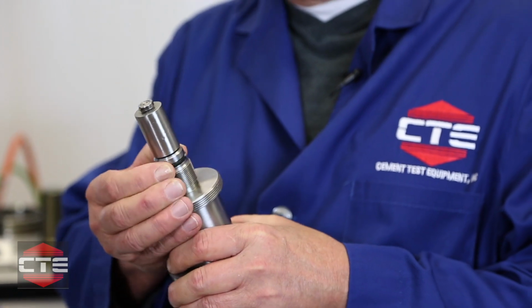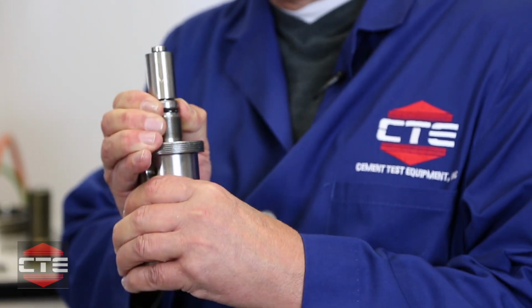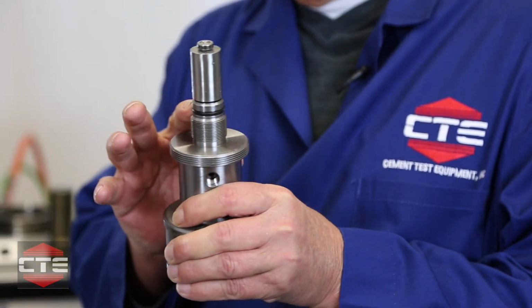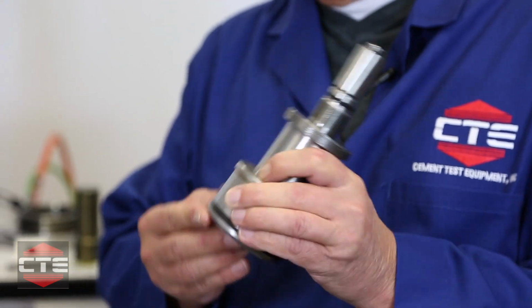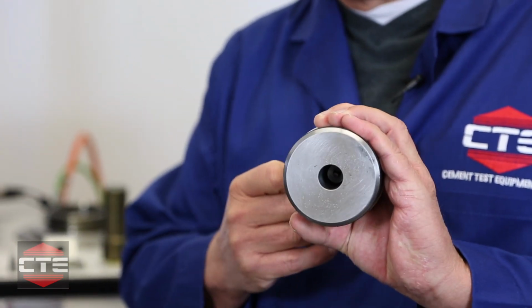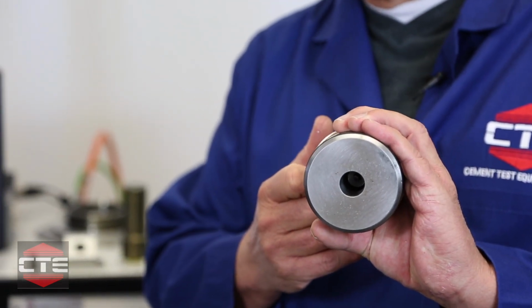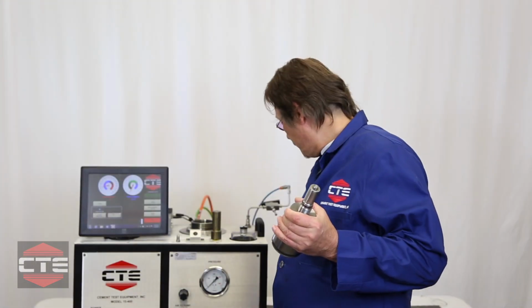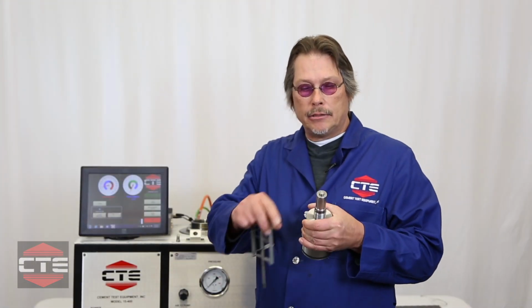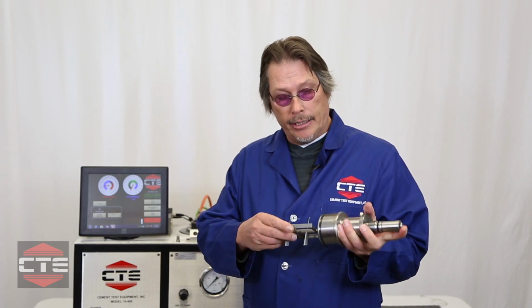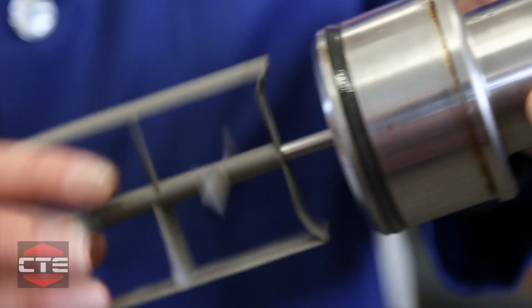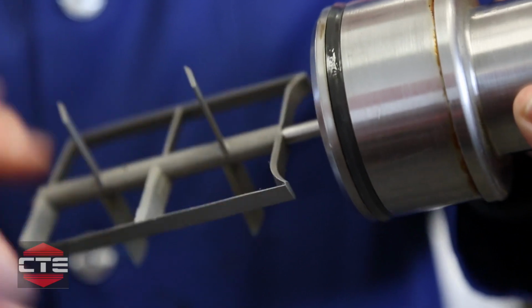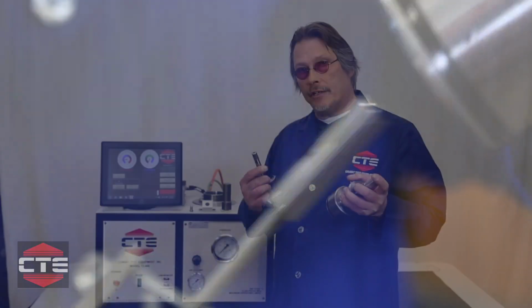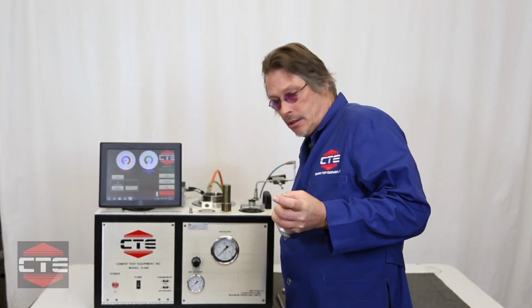So I'm going to go over how to change this poly pack and an associated poly pack C-1066 on the inside of the head, and we'll charge the head with oil, and then we'll be ready for a calibration. So the first step is to remove the inner magnet, which is accomplished by taking your slurry cup paddle, engaging it in the coupler, holding tension on the magnet as you unscrew the coupler. The coupler is disengaged from the mag shaft.